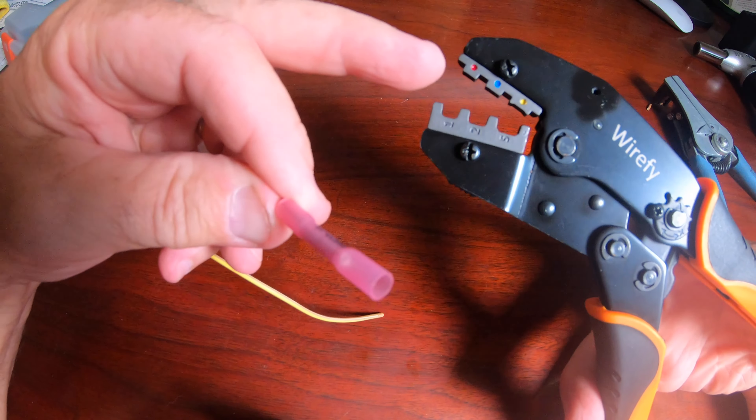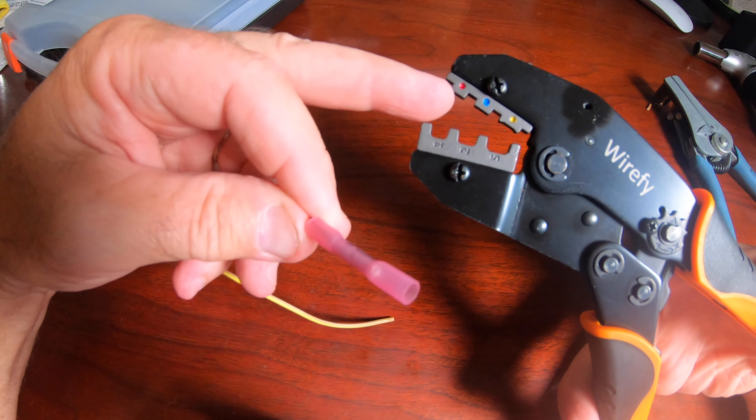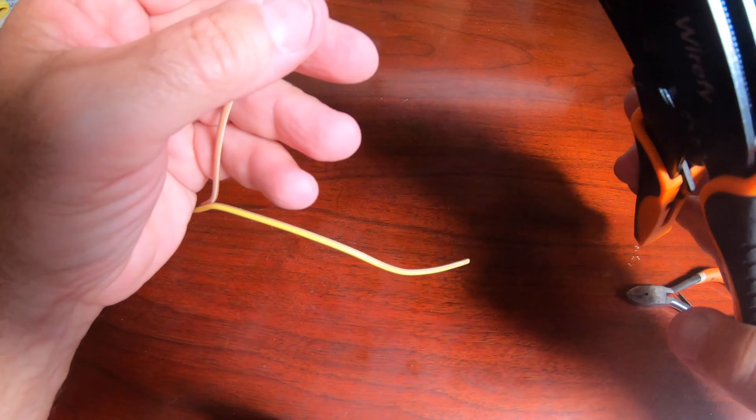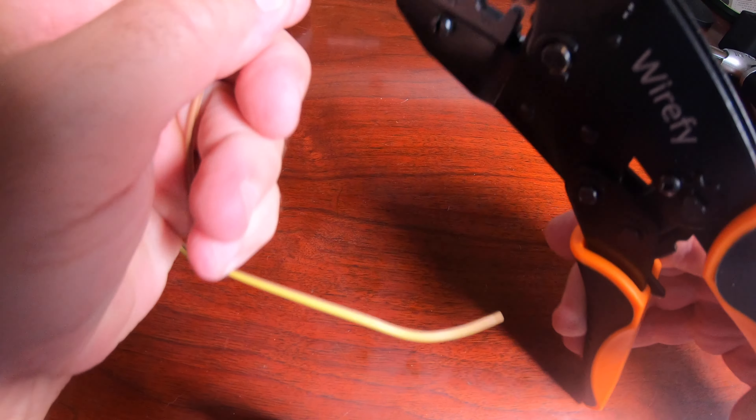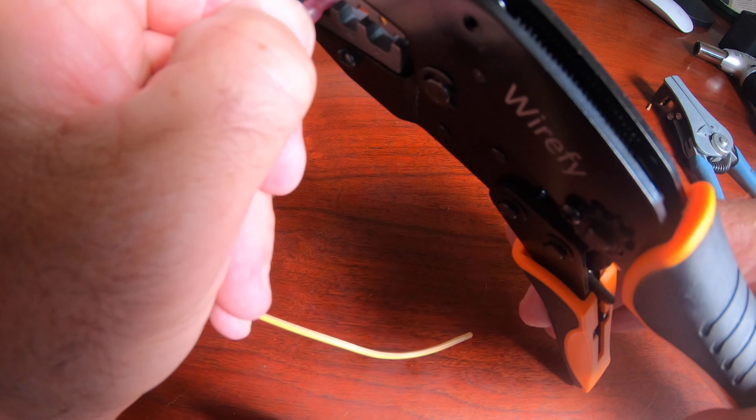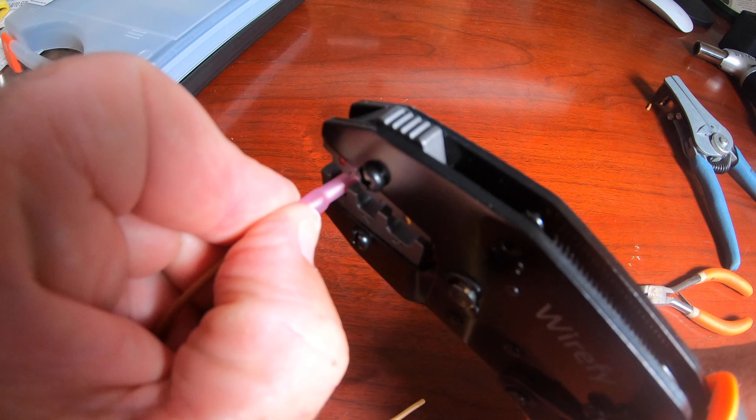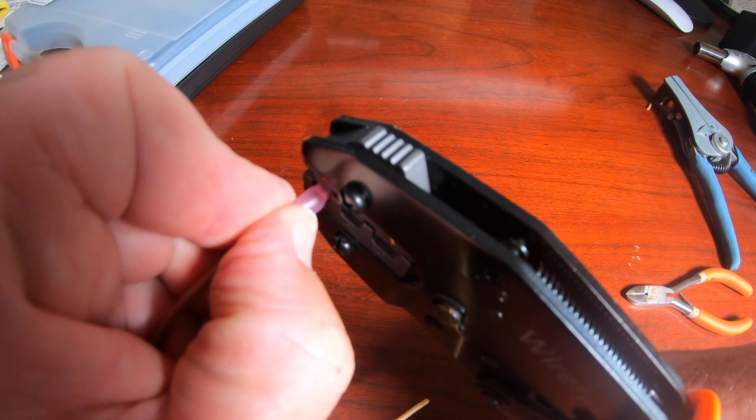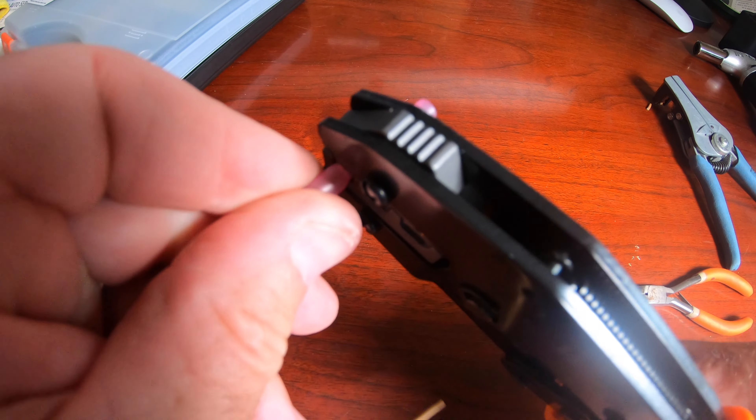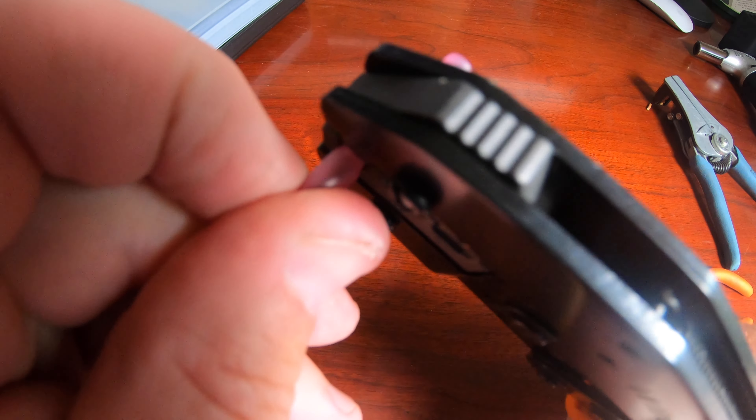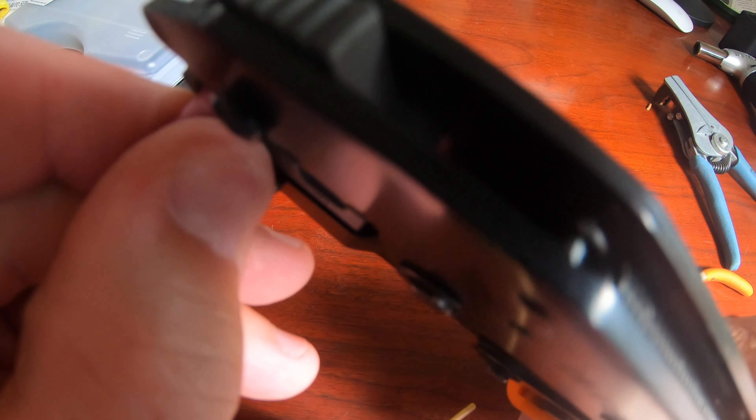The different colors represent the gauge wire and the appropriate connector that you use. The pink is for 22 to 18 gauge wire, the blue is for 16 to 14 gauge wire, and the yellow is for 12 to 10 gauge wire.